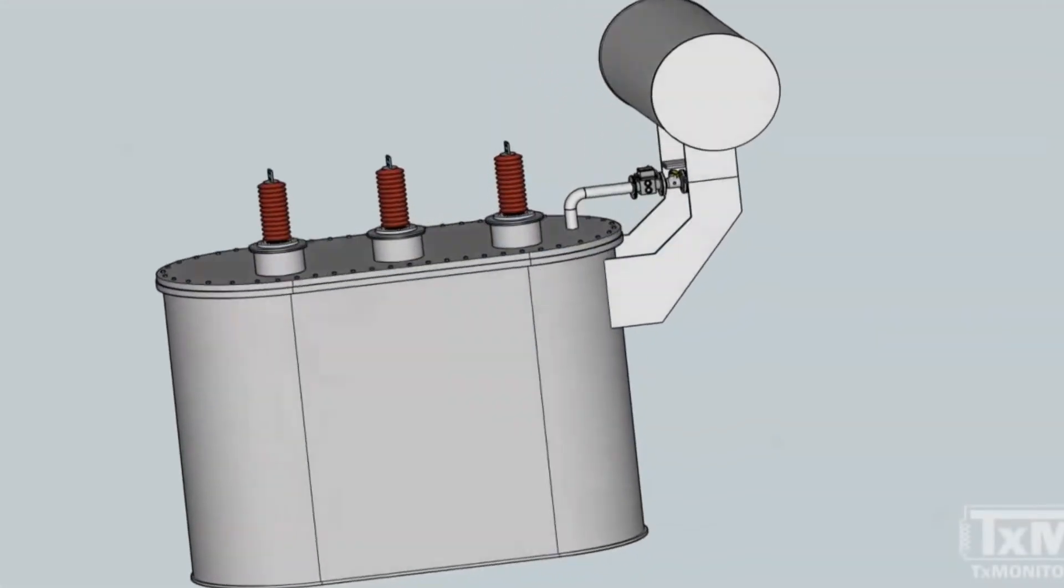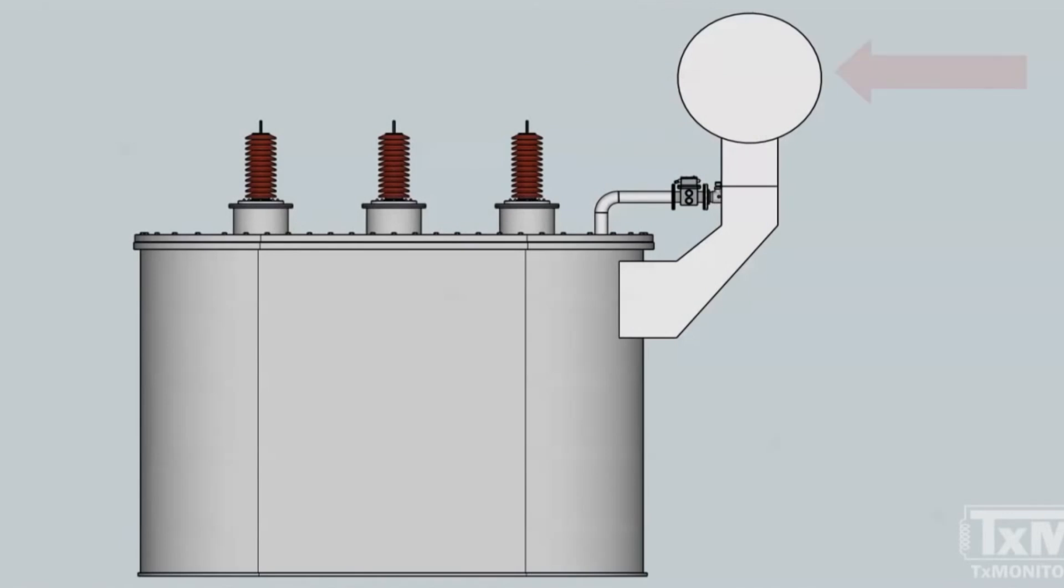On transformers, where the liquid preservation system design uses a conservator tank, a Buchholz relay is commonly fitted to provide protective functions and accumulate gases released from the transformer.